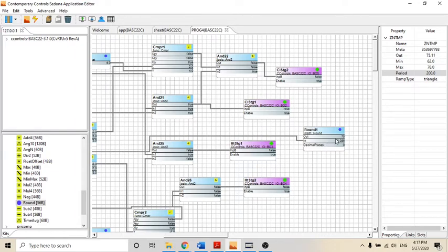75, it is switched. So right now the cooling just kicked in. We have cooling stage 1 on binary output number 2 would be true, so that would have triggered that relay and started the heat pump right then. The fan would have been working already. Now as it hits the 78 mark, the cooling stage number 2 will start working. The ramp is set to go to a maximum of 78 and then starts back. So as you can see, the air cooled off from there, and the ramp simulates this by going down.